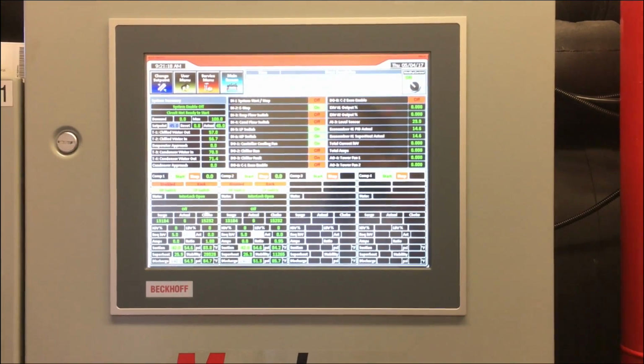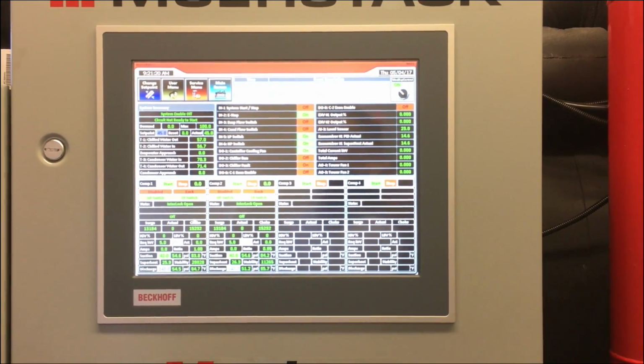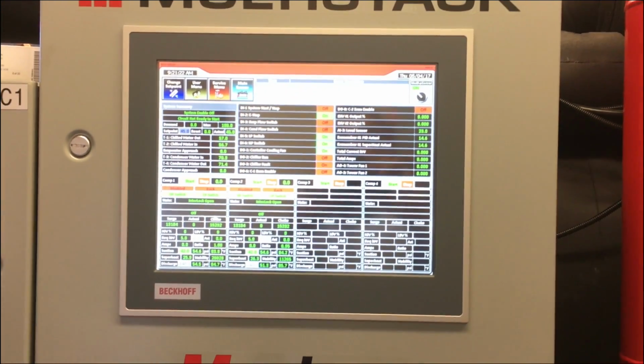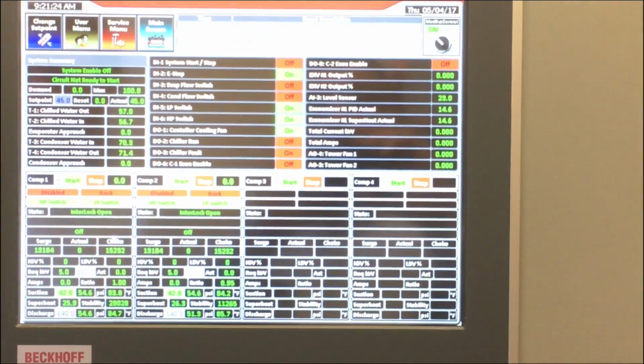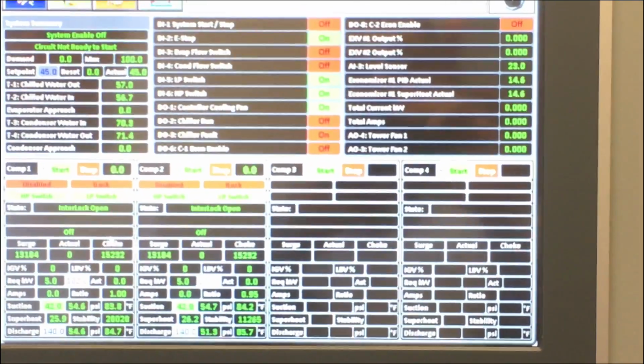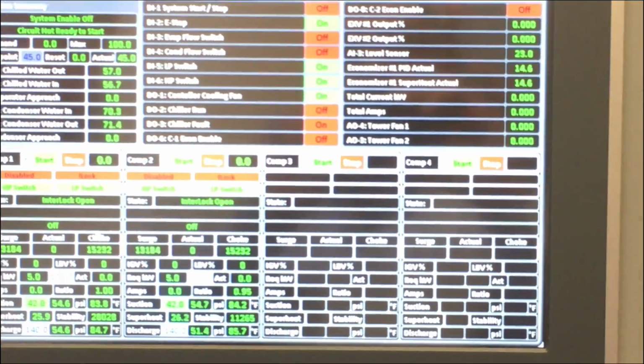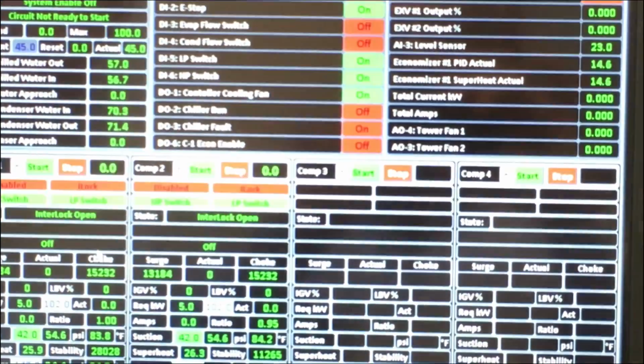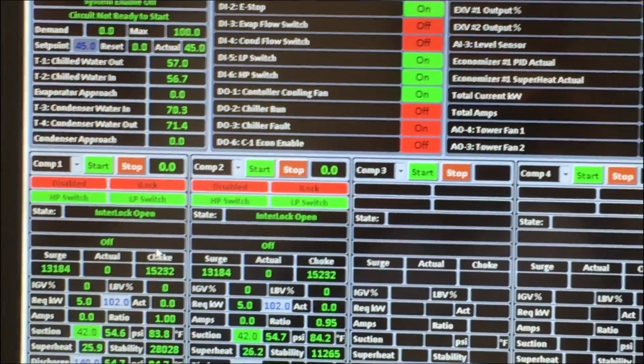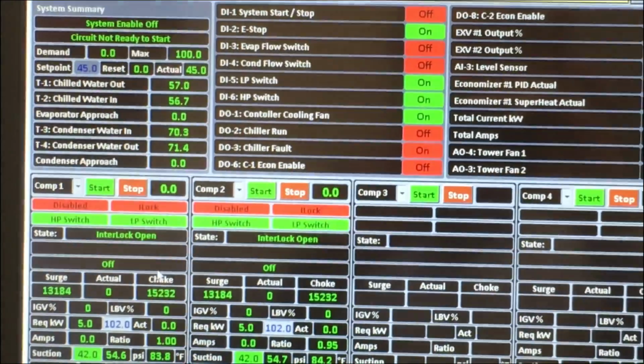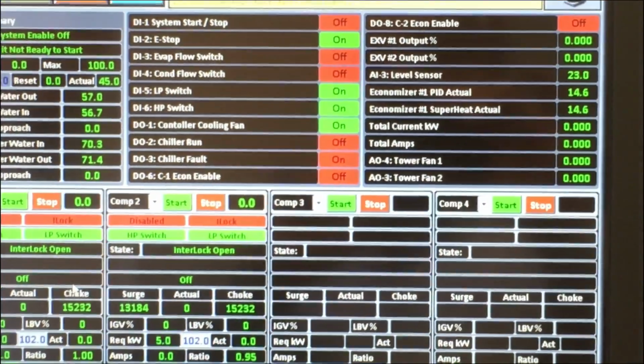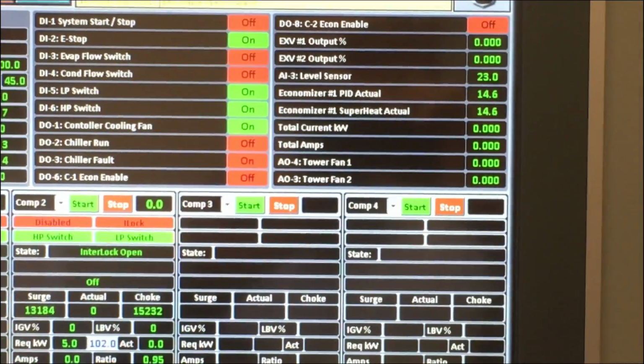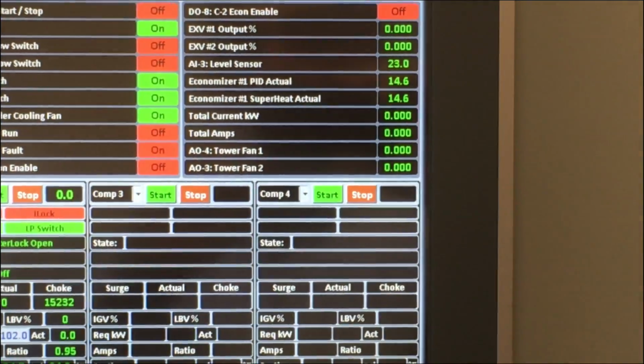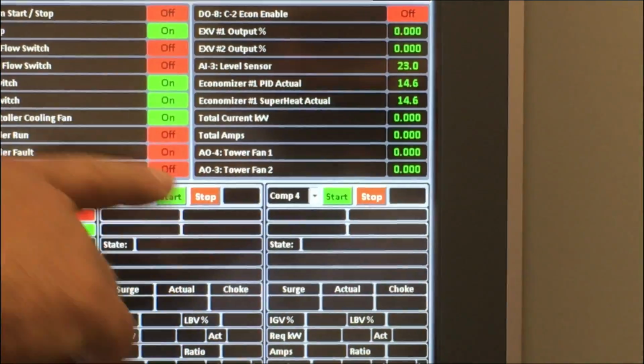And we only use it at 70% of our KW and higher because it saves about 4% energy, but only at the high end. It does very little work, if any, or maybe even hurts you at the low end. But at the high end, we can save 4% energy just by opening a solenoid. It's not bad. There's really no moving parts to it other than the EEV expansion valve. And then we have some outputs that show us the percentage of our expansion valves. Level sensor, which right now reads 23.